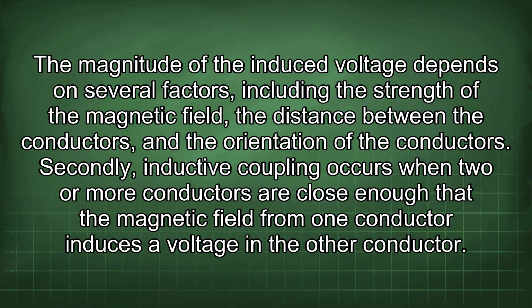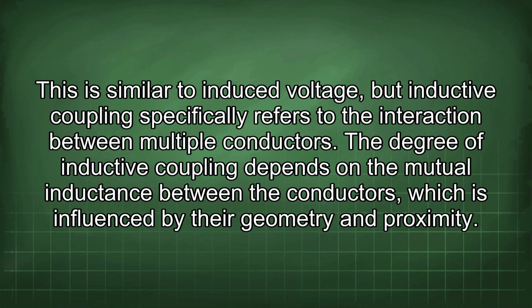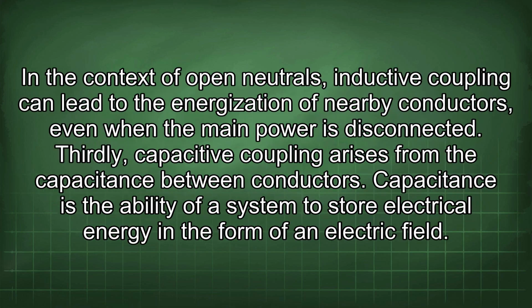Secondly, inductive coupling occurs when two or more conductors are close enough that the magnetic field from one conductor induces a voltage in the other conductor. This is similar to induced voltage, but inductive coupling specifically refers to the interaction between multiple conductors. The degree of inductive coupling depends on the mutual inductance between the conductors, which is influenced by their geometry and proximity. In the context of open neutrals, inductive coupling can lead to the energization of nearby conductors, even when the main power is disconnected.